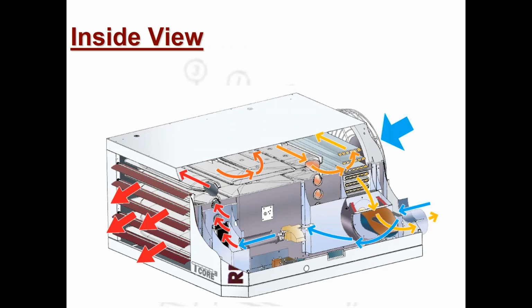This just gives you a view of what our condensing UEAS unit heater looks like. So from about midpoint where the gas valve is up to the front where the louvers are discharging the warm air, it's pretty much the same as our UDAP or UDAS unit heater. Same heat exchanger, a lot of the same components, same burner, same gas valves. But from the back end to the right, back to the propeller, that's where our secondary heat exchanger is, and that allows the unit to condense out and grab that extra latent energy that's in the flue gases to make it a true high-efficiency condensing appliance.